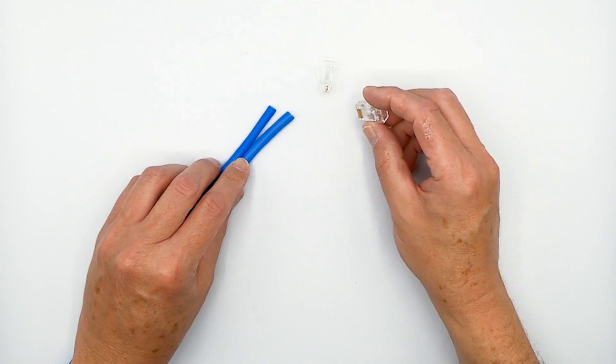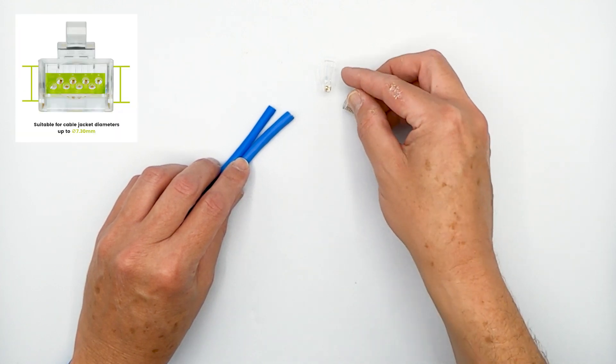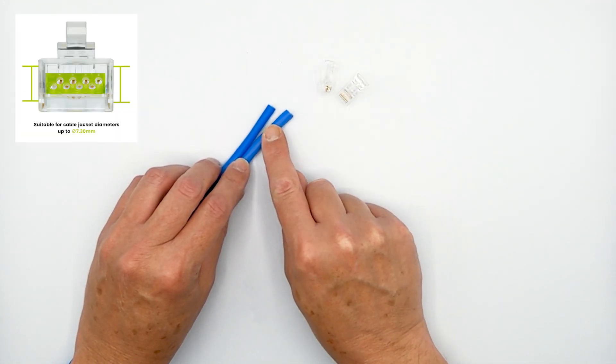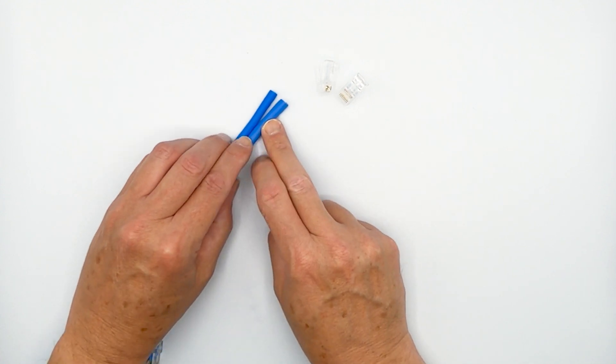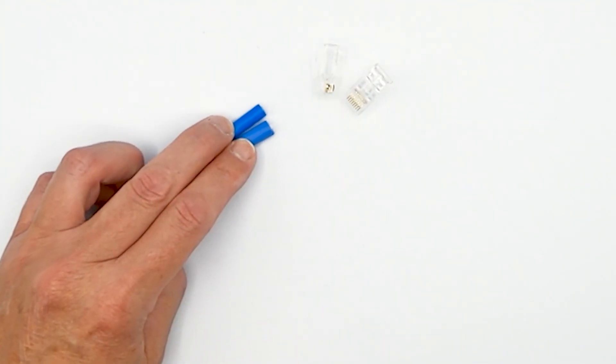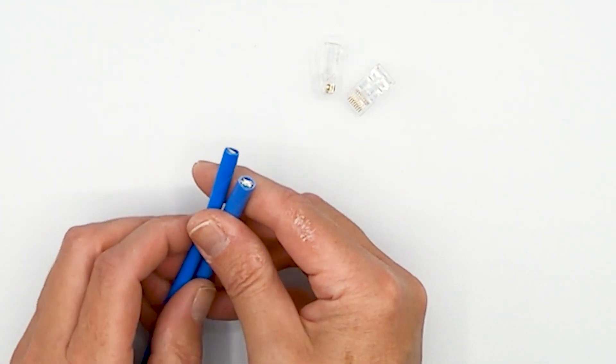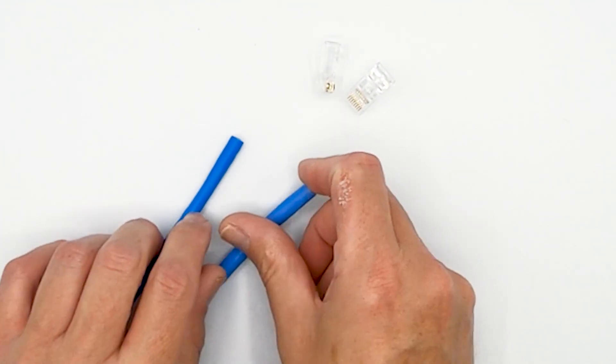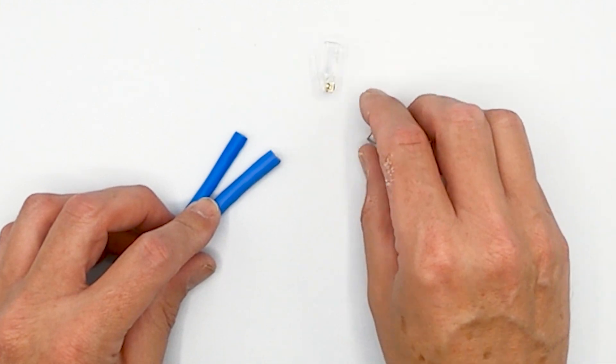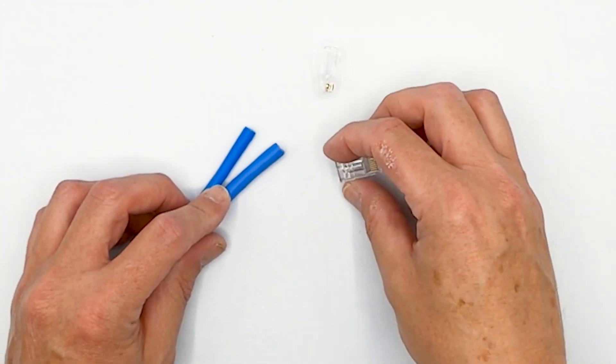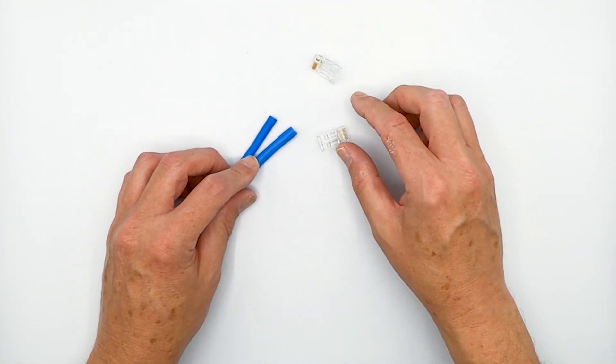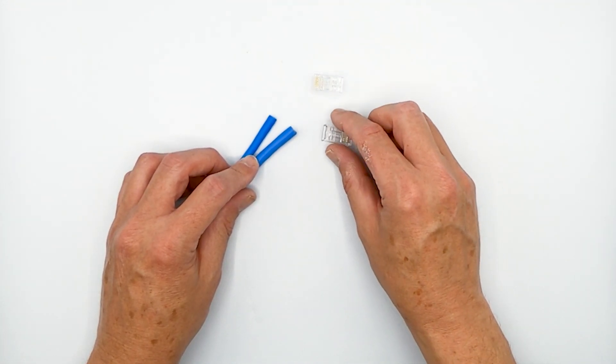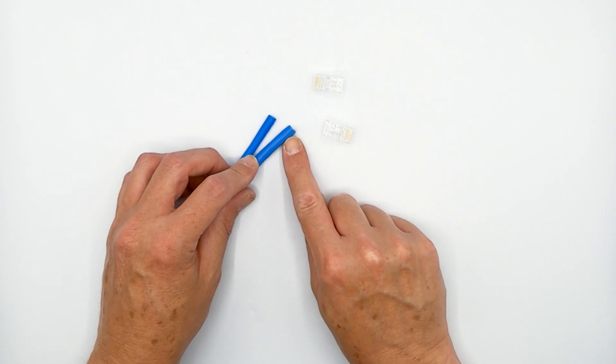We have our Category 6/6A plug and we have a Category 6A riser cable here and a Category 6 riser cable. And as you can tell, there is a significant difference in thickness between them. Some cables do need to be ovalized in order to get it to fit in the back of the plug.